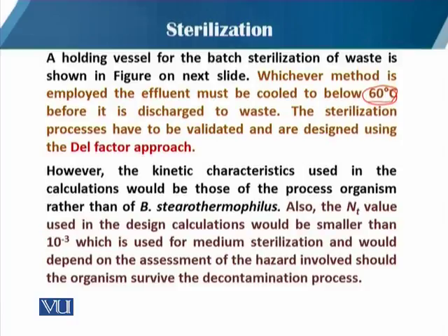The sterilization process has to be validated and designed using the Del factor approach, as we discussed in our previous modules. However, the kinetic characteristics used in the calculation would be those of the process organism rather than Bacillus stearothermophilus. As we know, our sterilization process is mostly designed keeping in mind Bacillus stearothermophilus, which is the indicator organism for sterilization. But as concerned the killing of the process organism, we have to select the method according to that particular organism.